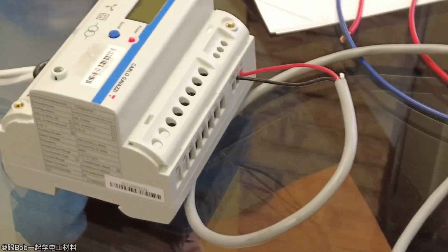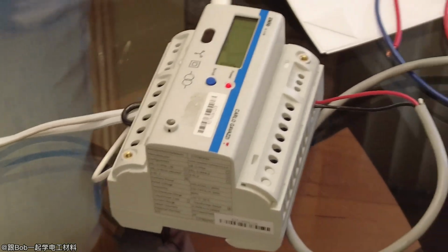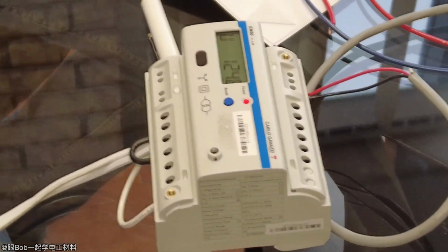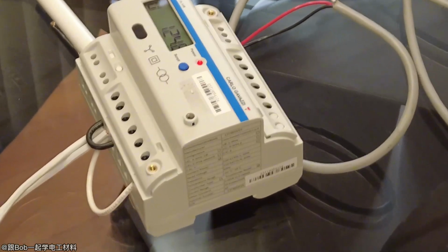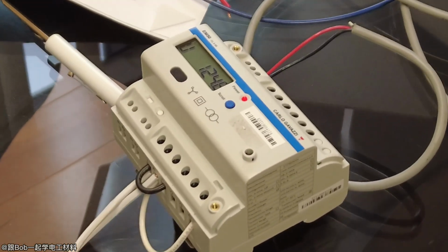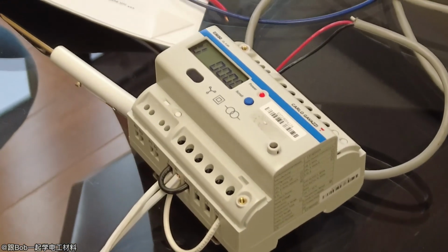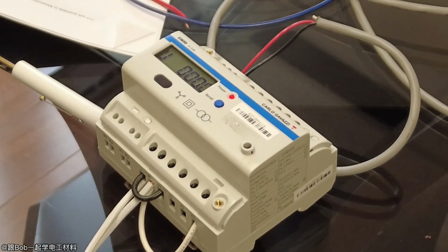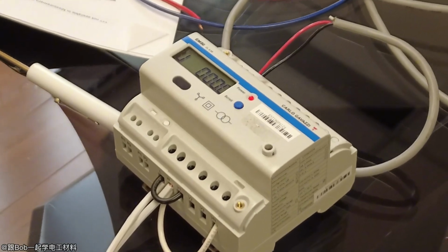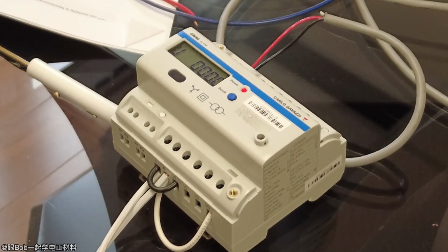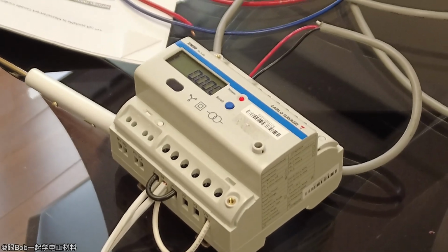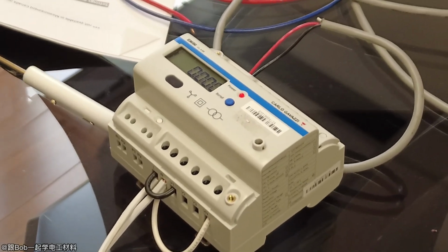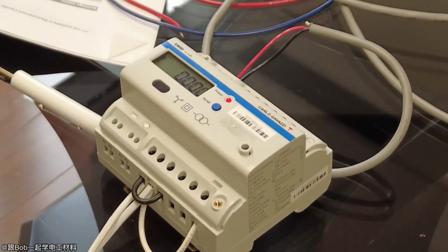Yeah, the flush mounted ones you showed us last time. Anyone that's doing building automation systems quite often wants BACnet. And our BACnet meters are BTL, which is BACnet Testing Laboratories, certified BACnet. Quite often if it's not certified BACnet, even though it has BACnet communication, they won't allow you to use it because it has to be tested. So if your meter has BACnet but it's not tested, you end up having to put a tested gateway in there, which just makes it more and more complicated.